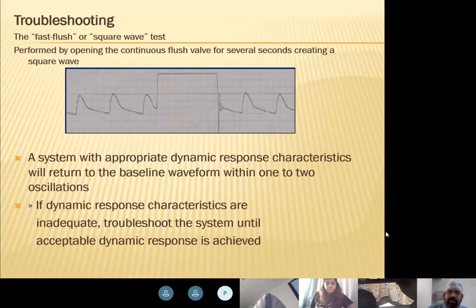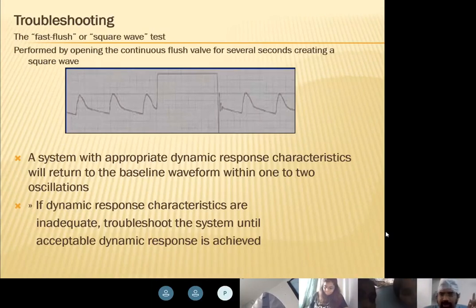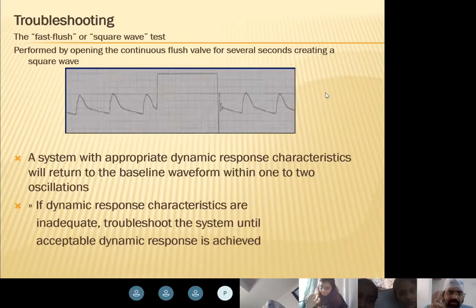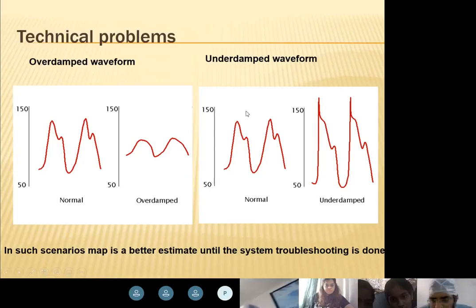So fluid goes inside. When fluid is suddenly going inside, what is the meaning? The transducer is exposed to the pressure on your bag. Are we clear? You're exposing the transducer to the pressure on your bag. Now, what is the pressure in the bag? The pressure in the bag is 300. So when the pressure in the bag is 300, where will your waveform go? When you made the scale on the arterial line, what is the scale over here? Let's go back to the waveform. See, our scale was 50 to 150, isn't it? This is your scale.